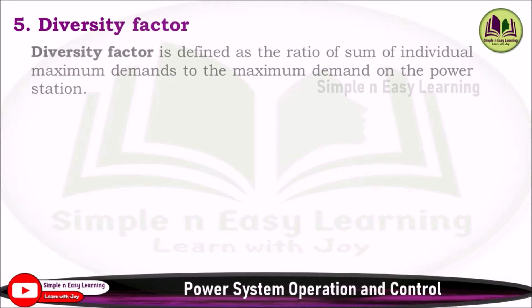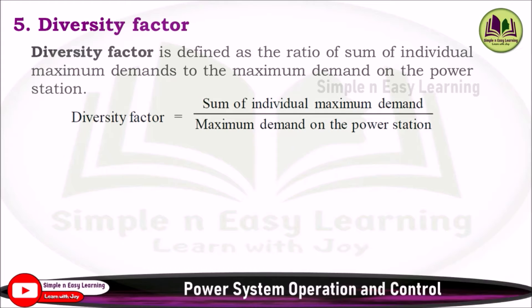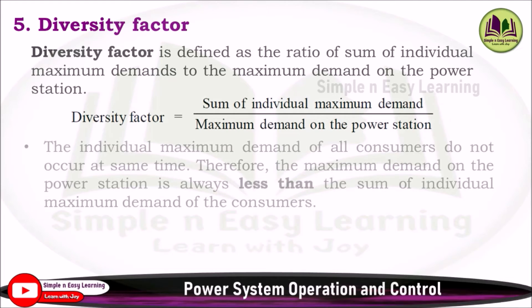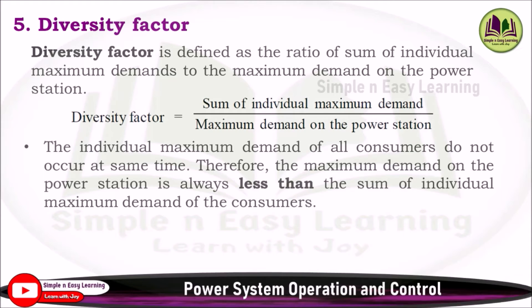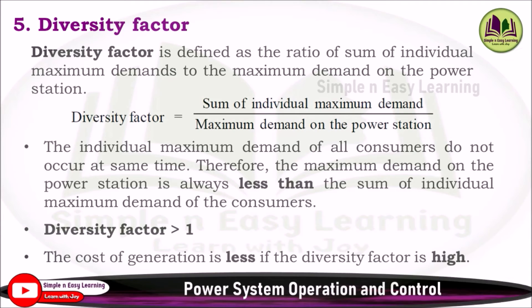Fifth: diversity factor. It is defined as the ratio of the sum of individual maximum demands to the maximum demand on the power station. Diversity Factor = (Sum of individual maximum demands of all consumers) / (Overall maximum demand on power station). Since individual maximum demands of consumers do not occur at the same time, the maximum demand on the power station is always less than the sum of individual maximum demands. Therefore diversity factor is always greater than 1. If diversity factor is high, the cost of generation is less.